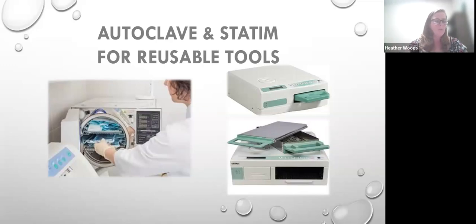Whereas the autoclave's cycle time is usually a little bit longer, 15 to 30 minutes. Their load capacity is larger. Their recommended spore testing is a little less frequent, and they may have a direct connection to water with lower maintenance. So it's good to ask your operators what their preference is and why, depending on their studio and their frequency of use. So you're going to observe different ones when you walk in there.